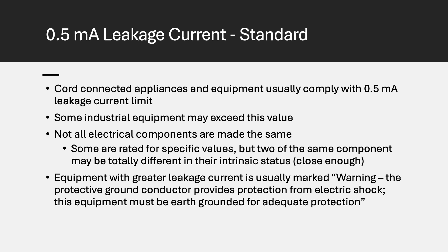Equipment that's dangerous because of greater leakage current is usually marked with a warning. The let-go current of 6 to 8 milliamps is considered the maximum current that a patient can tolerate and still release the conductor by using muscles directly stimulated by the current. Meaning 6 to 9 milliamps of current is the most you can stand and still decide to let go of whatever is shocking you, because it's not quite enough to totally take over the electricity controlling you.